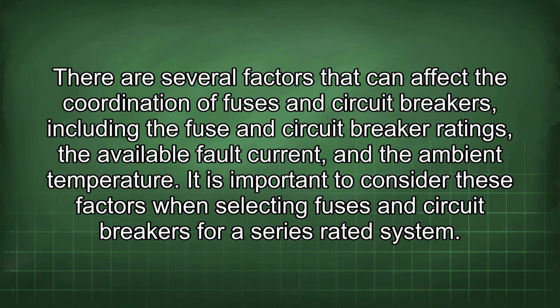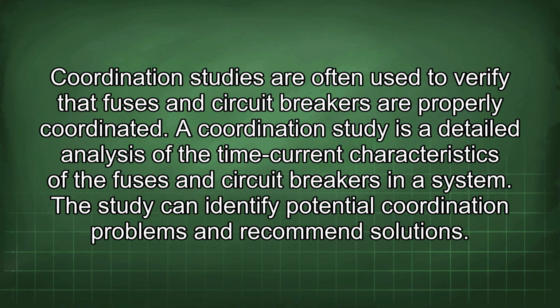There are several factors that can affect the coordination of fuses and circuit breakers, including the fuse and circuit breaker ratings, the available fault current, and the ambient temperature. It is important to consider these factors when selecting fuses and circuit breakers for a series-rated system. Coordination studies are often used to verify that fuses and circuit breakers are properly coordinated. A coordination study is a detailed analysis of the time current characteristics of the fuses and circuit breakers in a system. The study can identify potential coordination problems and recommend solutions.